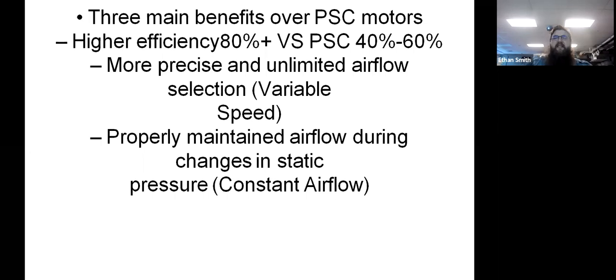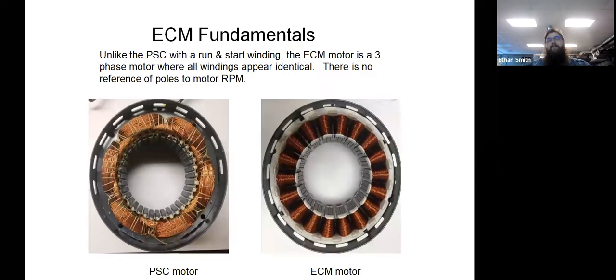This is not to say that a variable speed blower motor is the cure for bad ductwork, much to the contrary. The only cure for bad ductwork, guys, is good ductwork. What a variable speed motor will do to your bad ductwork is make it louder. Okay, it will also shorten the life of the ECM.